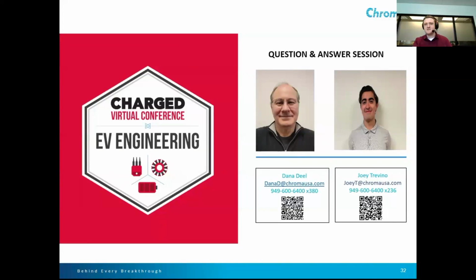All right, for the next question, we have, can you use regenerative test equipment to power one another? The regenerative equipment can be used to power each other, but they both need to be connected to the grid. You can't just have one unit directly connected to the other. They both have to be connected to the grid, receiving input power from the grid, but the regenerative power will go back and redistribute through the panel, facility, anything to the other unit. So it does power each other in that way.